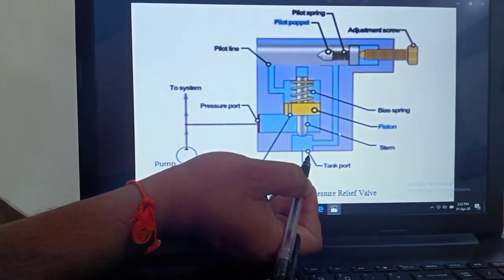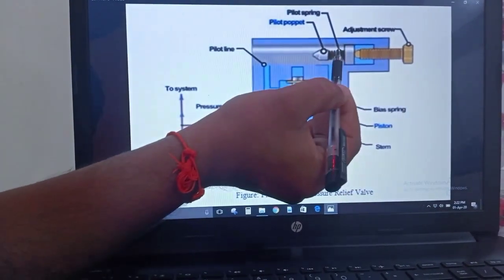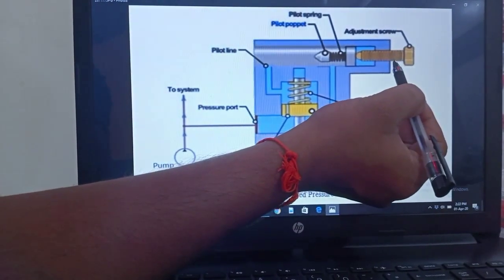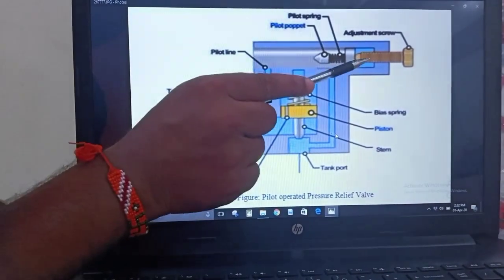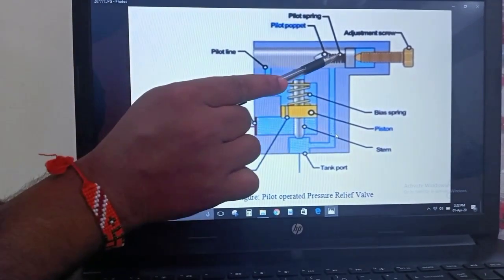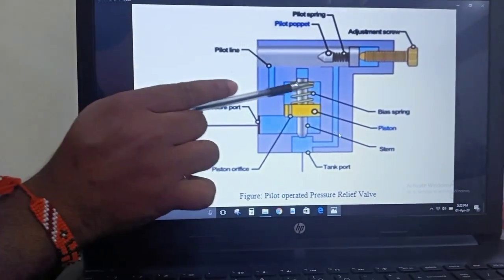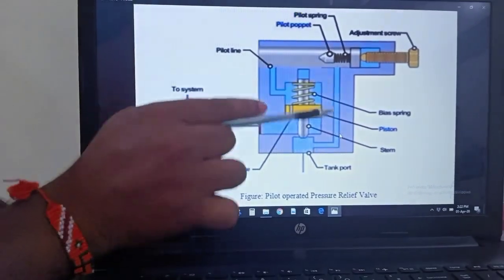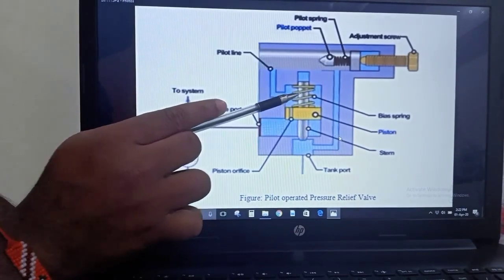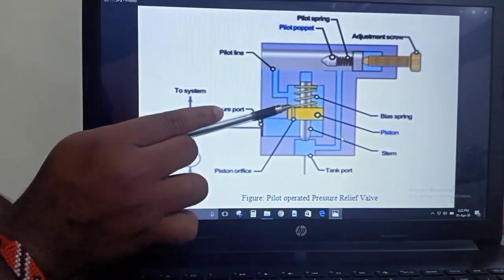The pilot relief valve consists of an adjustable screw, a spring, and a poppet. The adjustable screw is provided to vary the spring force over a specified range of pressure. The main relief valve consists of a piston, a stem, a spring, and a small orifice which is drilled through it.